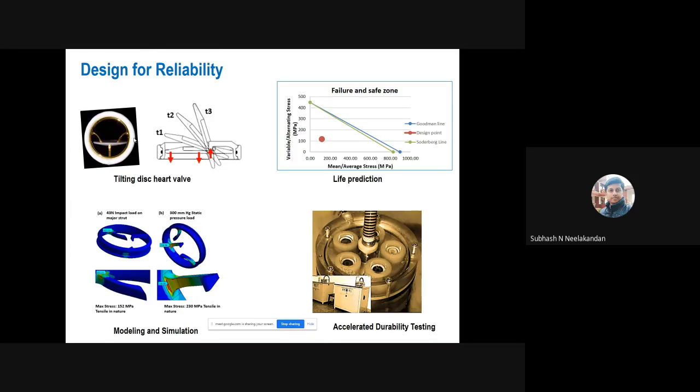And unlike automobile devices or home appliances, we don't have a maintenance schedule or a chance to do maintenance because it's a surgical procedure. Once it is done, it is done, until and unless there is a medical emergency. So the device should be designed in such a way that without any maintenance or corrective action, it should work the same for 50 years. So how can we do that? It can be executed through a method called DFR.